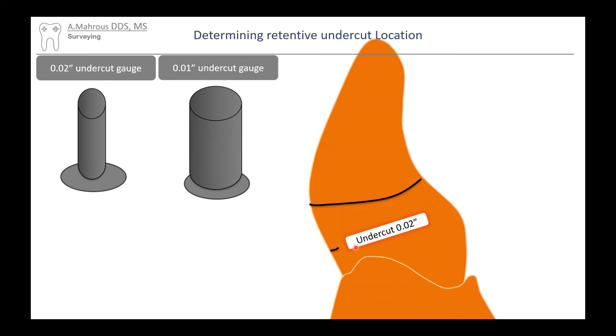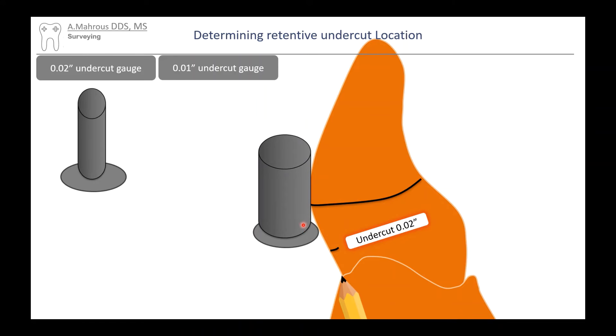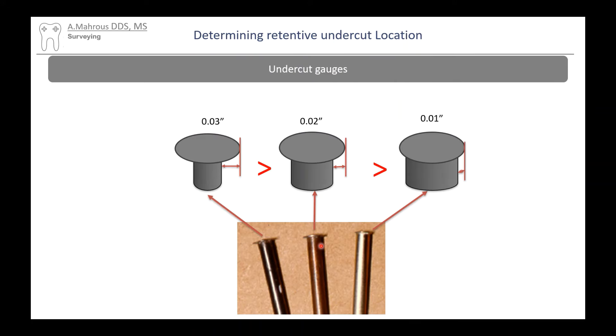You can see if we use a 0.01 undercut gauge, again, moving it so that the shank and the disc touch, that disc will now be considered touching at a 0.01 undercut. In this slide here, you can appreciate the difference in distance representing the 0.03, 0.02, and 0.01 undercuts.